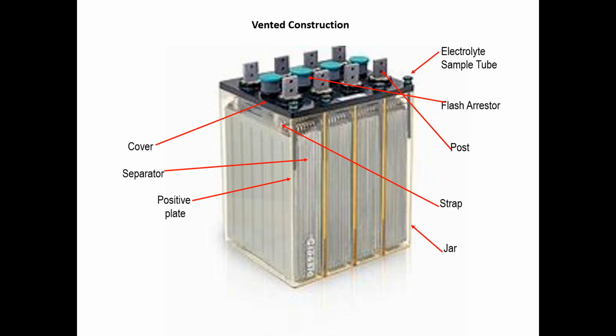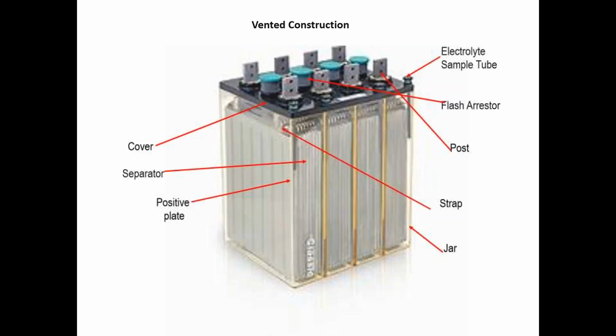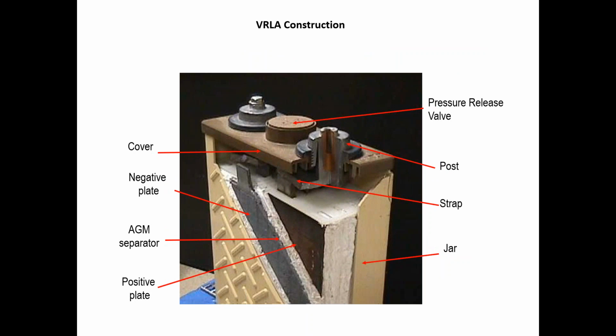As these batteries are in operation, they off-gas hydrogen and oxygen, so there's consideration that has to be made for ventilation. And again, these jars are somewhat, I'll say, fragile during installation. They're usually a PVC or a polycarbonate material that can break. So you have to be careful when handling it, working around any battery, but these in particular, and primarily on installation and de-installation. You have a lot of the same components in the valve regulated, cover, negative plate, positive plate.